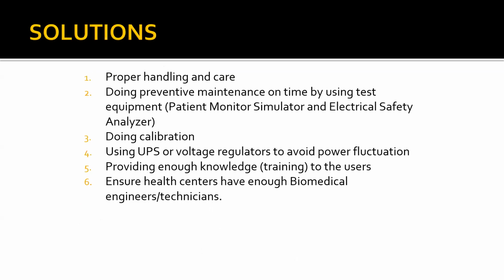So to keep the patient monitor working properly, you need to do proper handling and care. Basically, you need to train the users and do preventive maintenance on time by using test equipment. If you have all the test equipment, do it in the proper way, doing calibration. In certain places you need to use a UPS or stabilizer to avoid power fluctuation.